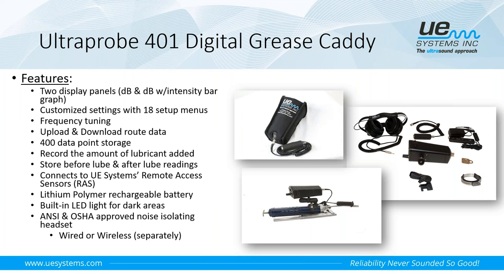The good thing about the Ultraprobe 401 is it does work with our remote access sensors, or the RAS sensors that many of you are familiar with. These would be in use if you have equipment that is inaccessible due to distance or safety or guarding. You can go in when it's safe to do so, mount the sensor, and then run the cable out, and it'll plug in directly to the Ultraprobe. Or you can bring as many as eight of those RASs together to one location, to an eight-channel junction box, and then you can just simply plug in from the junction box to the Ultraprobe, and we can take as many as eight readings from one location.